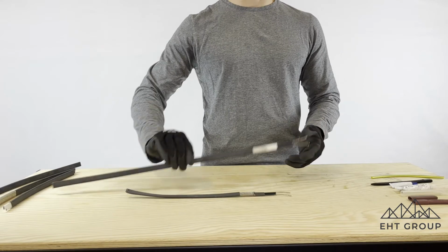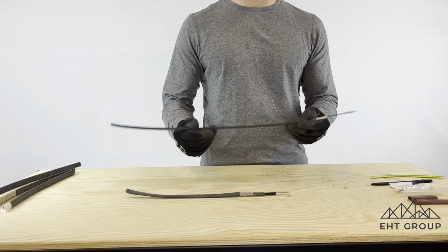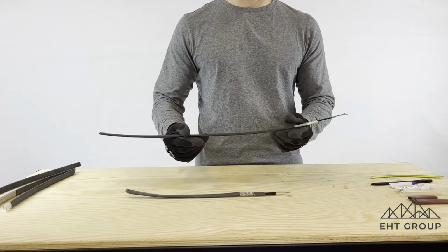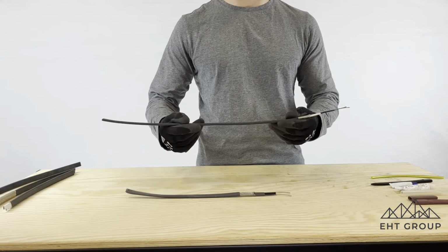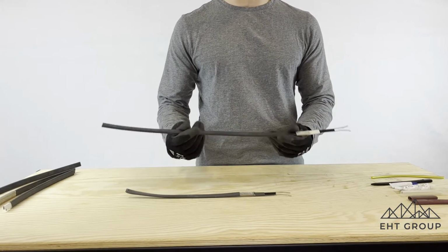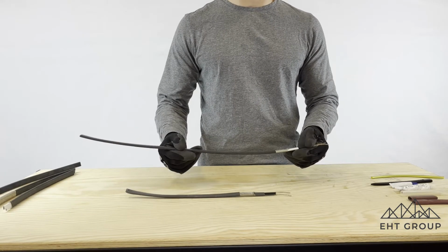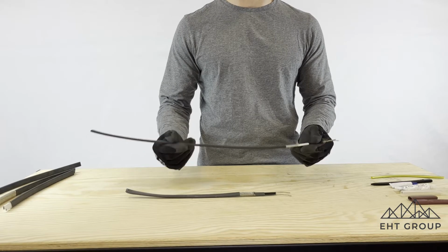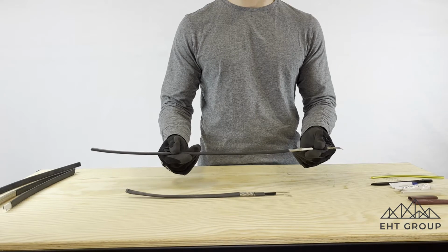So SR cable is a cut-to-length heat trace cable. It comes on a spool, and from an installation point of view it makes installation quite easy, because you're just ordering this cable on a spool and then you're just installing it. There are also no sheath temperature concerns with an SR cable. Where some applications have hazardous environments and there's an auto ignition temperature concern, SR cable does not. There's no concern when using SR cable for those applications.